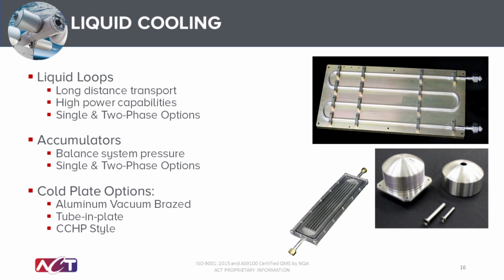In these large systems, with temperature changes, everything will expand and contract. So accumulators are what we need to use to keep the pressure consistent, or we can vary pressure as well with a more active accumulator. There are two main types of accumulators, single and two-phase. Single phase accumulators are typically a bellows type, where a spring holds a constant pressure, and the bellows accounts for changes in volume.